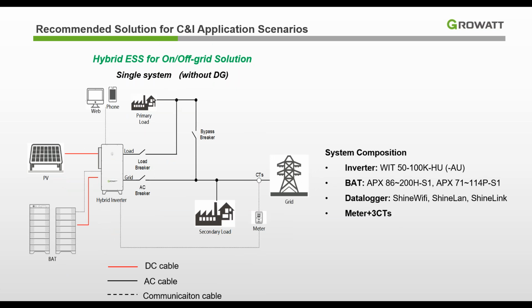The next is the on or off grid solutions, where we can switch from the on-grid mode to the off-grid mode. That would be similar to the on-grid solution, but the difference is you will separate your loads: one is the backup, the primary loads, and the secondary, which is non-backup loads. If you want to even switch to off-grid, then link your primary loads to the load port on the inverters. So normally when it's on grid, there's a bypass breaker.